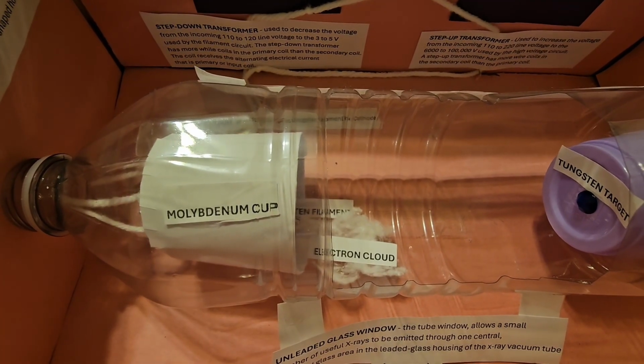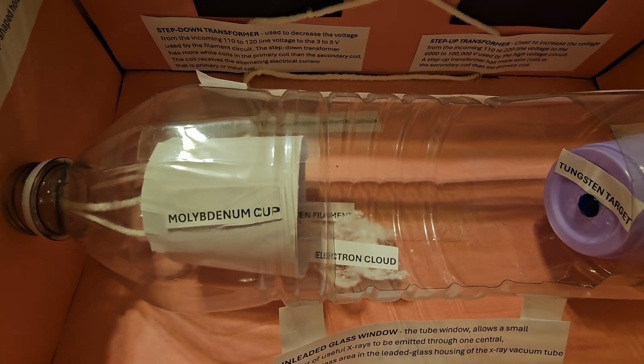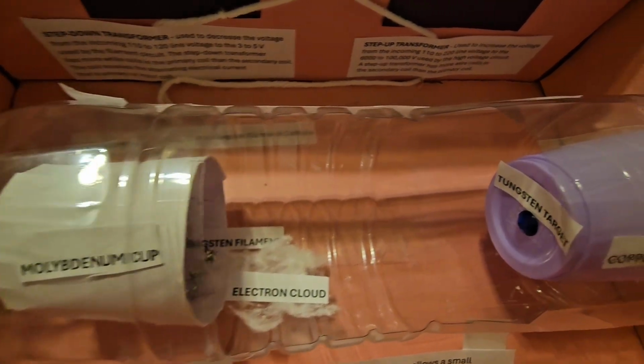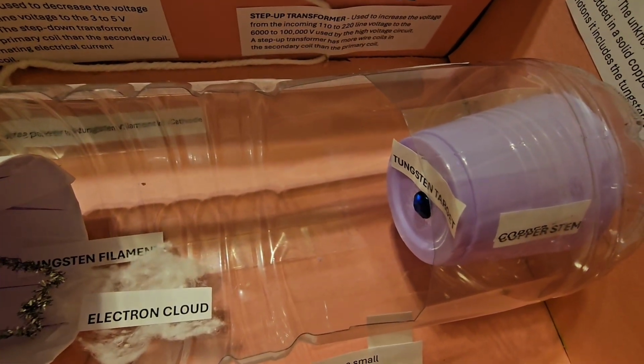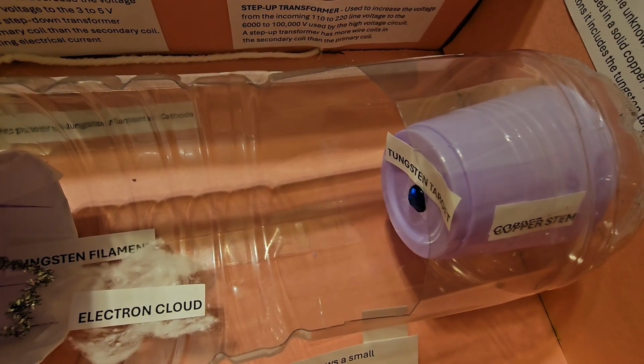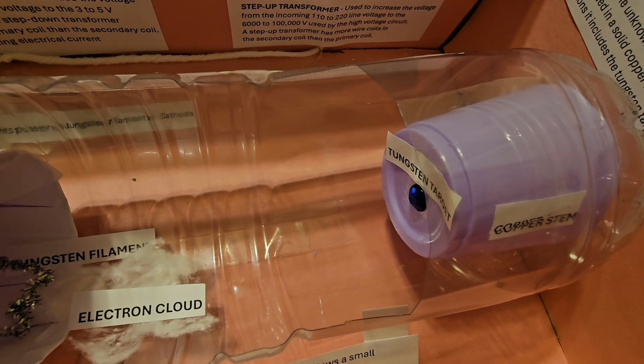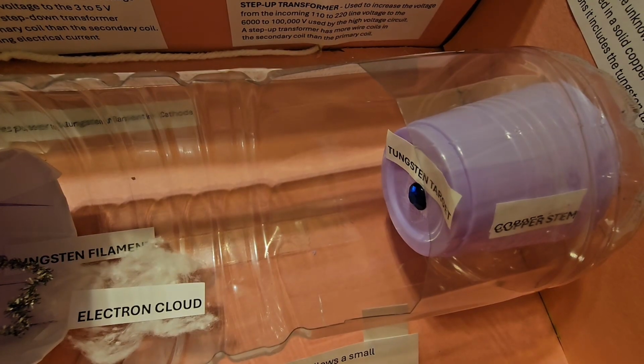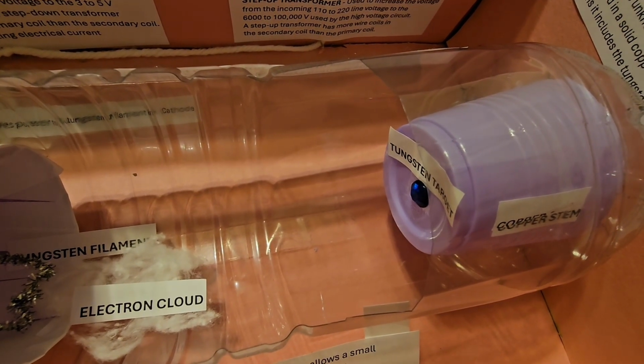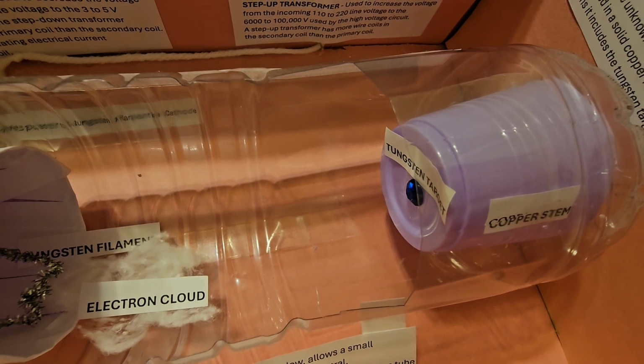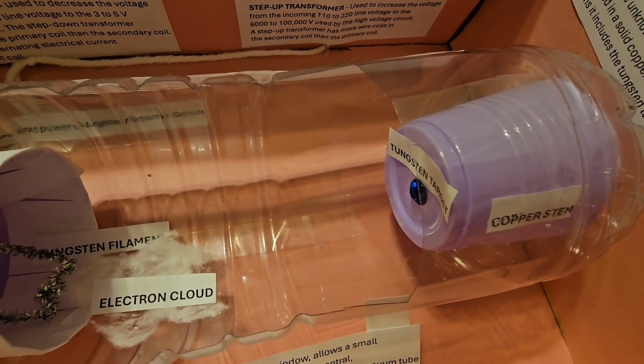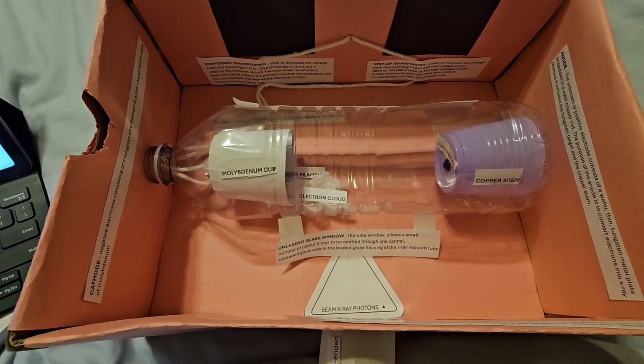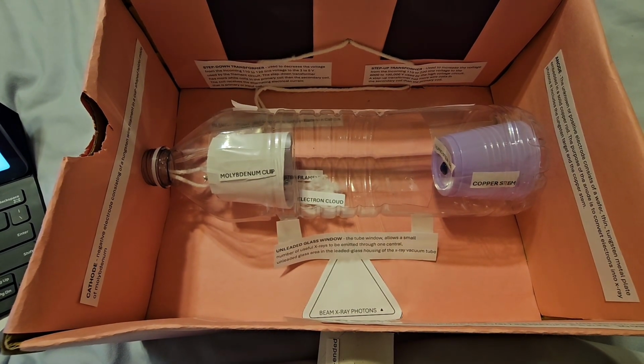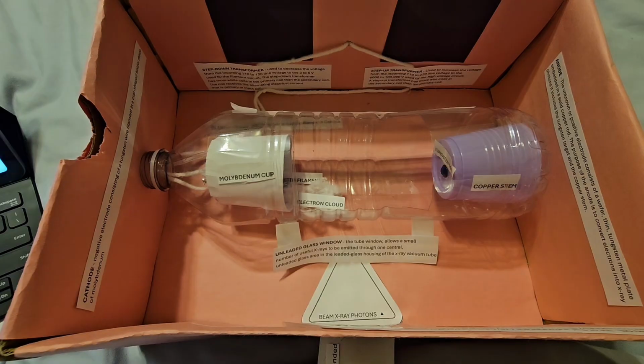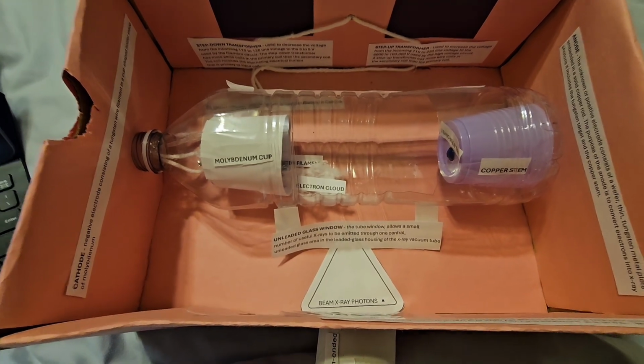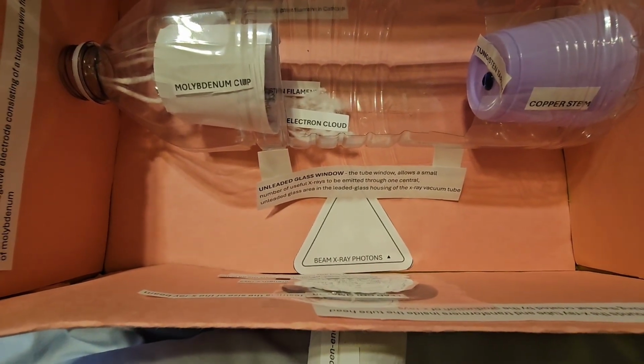When the exposure button is pushed, the high voltage is applied and the electrons produced at the cathode are accelerated across the tube towards the anode. The electrons strike the tungsten target of the anode and their kinetic energy is converted into X-ray energy and heat. About 99% of the energy is heat, which is carried away by the copper stem and absorbed by the insulating oil, while about 1% becomes useful X-rays. The X-rays are then produced and emitted from the target in all directions. The leaded glass housing prevents the X-rays from escaping, except through a small unleaded glass window portion of the tube.